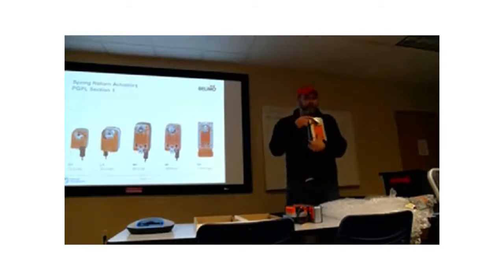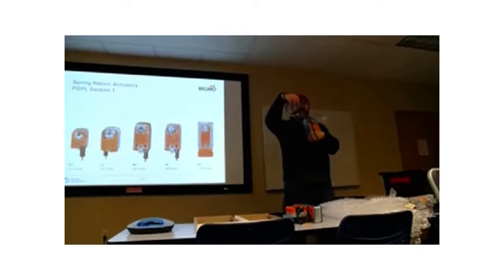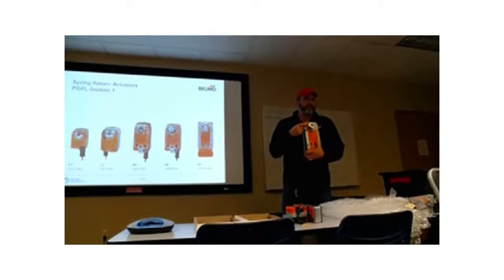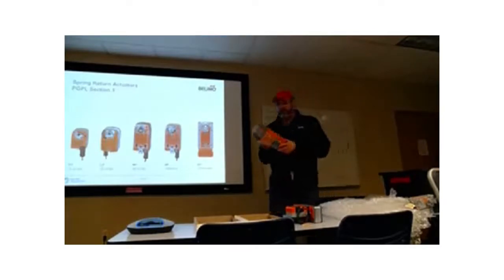If you look in the upper corners of the actuator, you'll notice it has 2 cable whips. One's for power and signal, and this is the switch cable. The switch is adjustable up here in the front. I think the fixed rotation of the lower end is 10 degrees, and you can adjust it from 10 to 85 on the upper end. That's how you set it in the field.